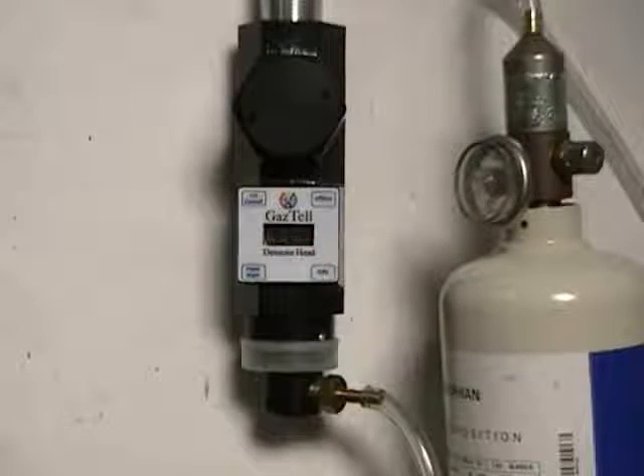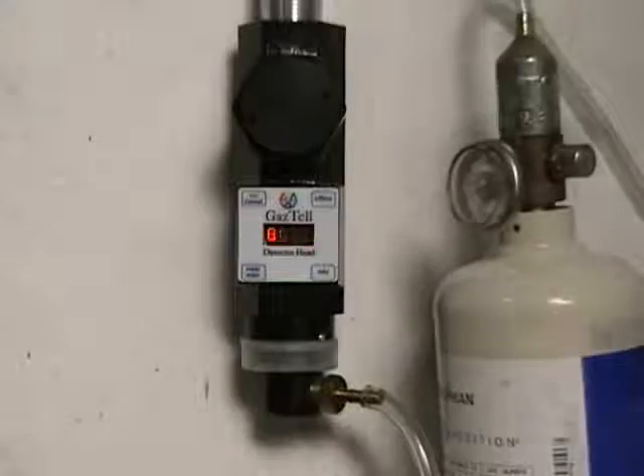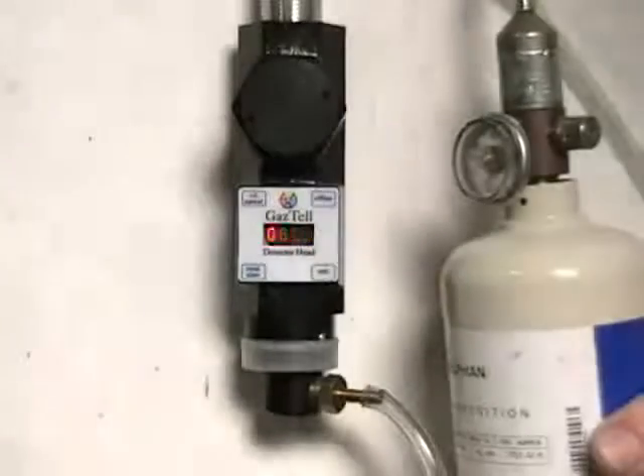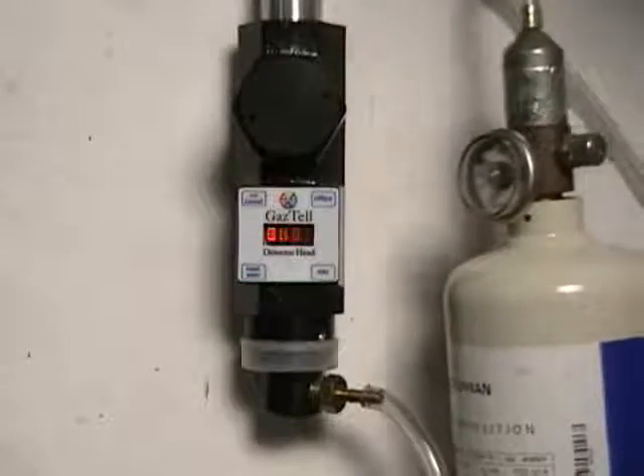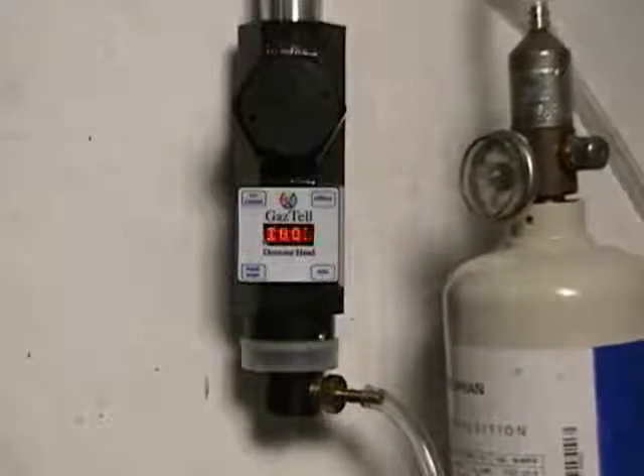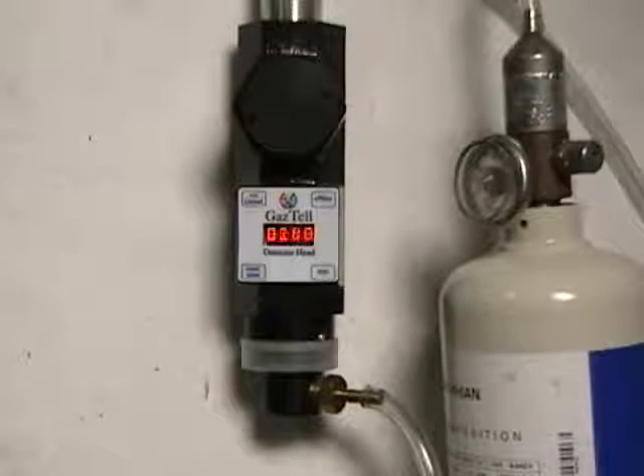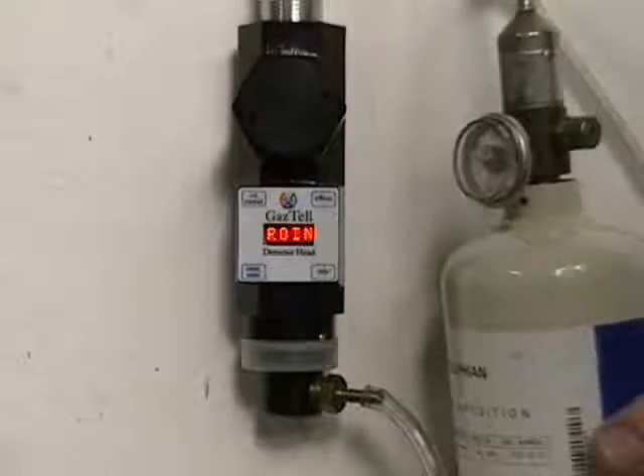After a successful zero calibration, zero OK will be displayed. If you get a calibration error, calibration has failed. An unsuccessful calibration may indicate an erratic sensor, a bad zero, or bad zero gas. You should make more than one attempt to calibrate zero.